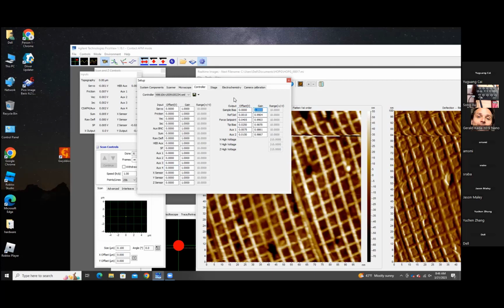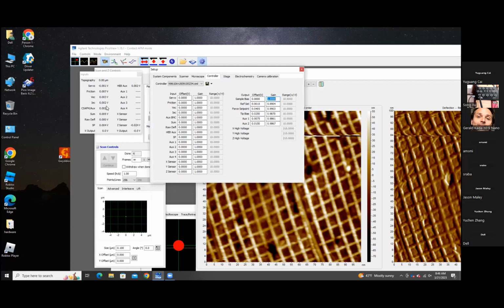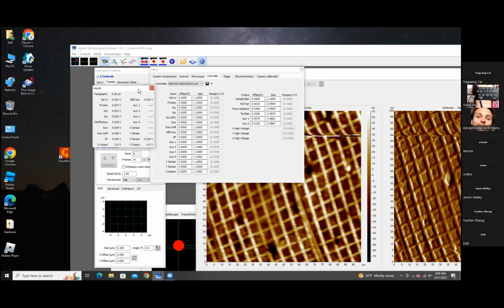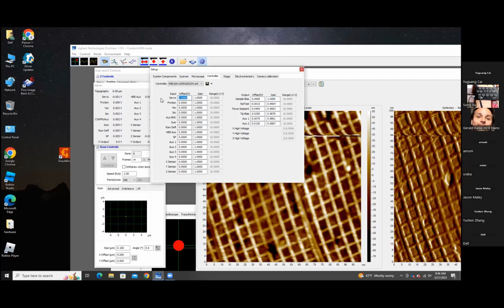If you look at your inputs, those values that are drifting again, you'll notice that they all line up to a calibration file parameter that you can adjust, right? So we're looking at servo at the very top. You've got negative 0.001, 0.002. It's kind of fluctuating between. Go to your offset in your setup window and just put in the opposite value of what you're seeing. So put in 0.0015. You've got a little bit more room to play with and it'll show. And notice, bam, right out the gate, you're back to 0. I see. So what we're trying to achieve on every one of these inputs is to add the offset. So go ahead and just put the opposite value in.